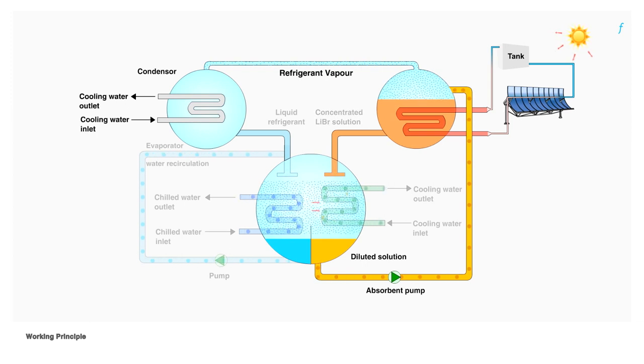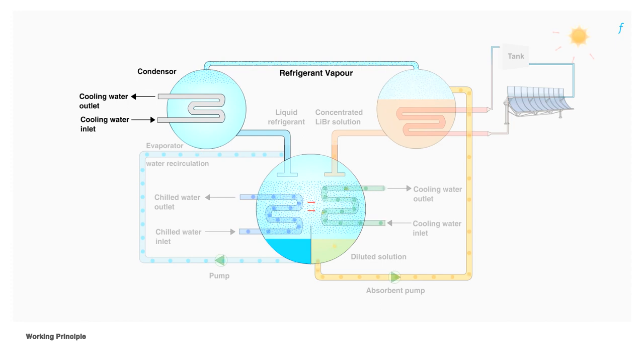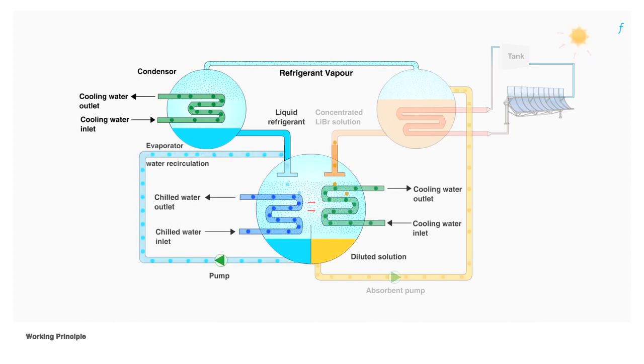Water vapor from the generator is not allowed to escape and is directed to a separate chamber called the condenser, where it is stored. This vapor is condensed by bringing it in contact with tubes containing water from the cooling tower. The condensed refrigerant is made to enter the evaporator, where it vaporizes due to the prevailing low pressure conditions, while passing over the chilled water tubes.